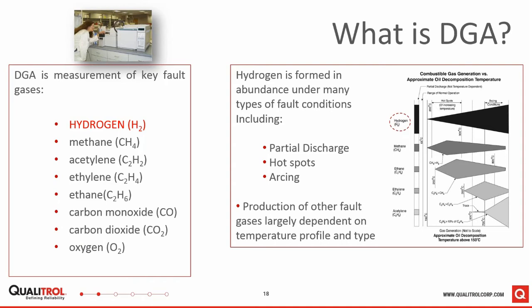As the temperature continues to rise, the concentration of the gases that are produced changes, but if you notice for hydrogen, it's always increasing. So hydrogen is considered to be a universal fault gas, and it is produced when there are partial discharges, when there are hot spots in the transformer, as a result of arcing. The production of the other fault gases is dependent on the temperature profile within the transformer, but hydrogen is always produced, a universal fault gas.